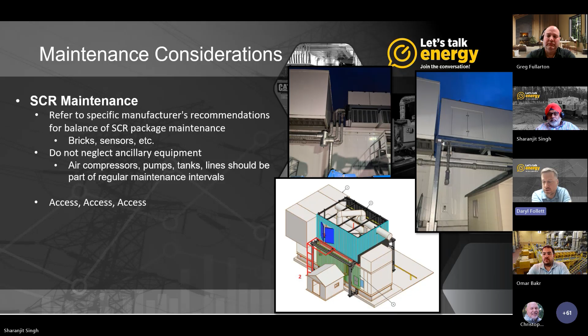On testing and maintenance, ensure you're aligning your SCR maintenance and testing with your generator testing. It's the best time to make sure you're seeing the right reduction and the right emissions control. As mentioned, there are repeated stack tests needed in some situations, and you don't want to find out you have a challenge, or that an adjustment or recommissioning is needed on your equipment.